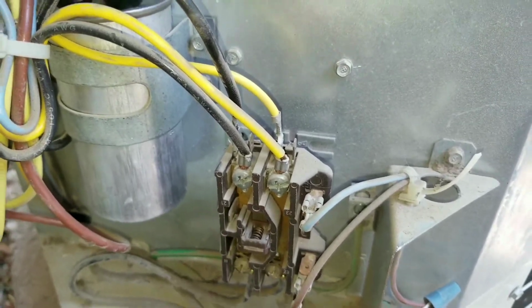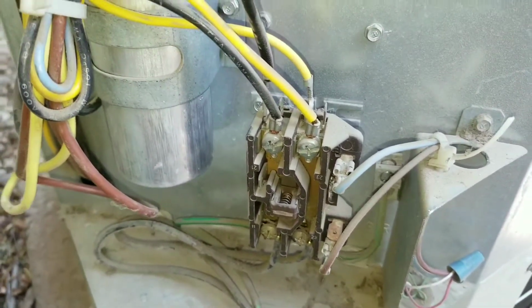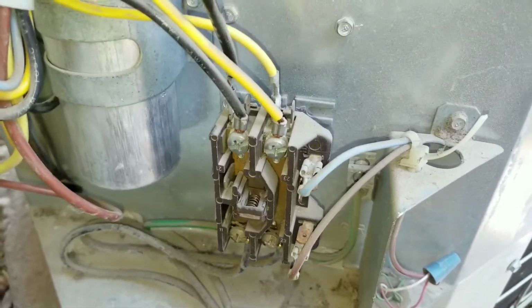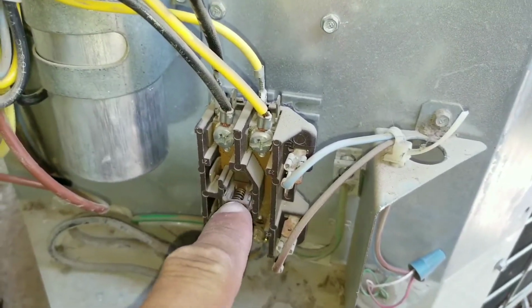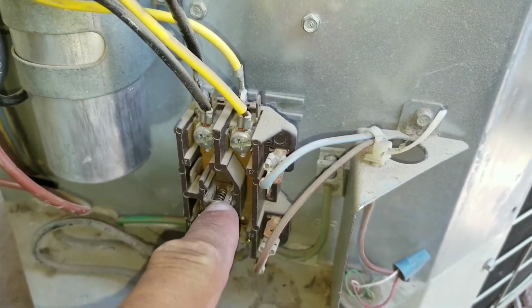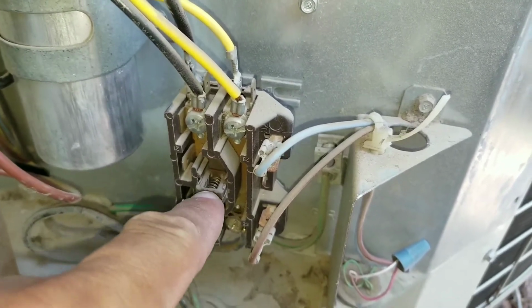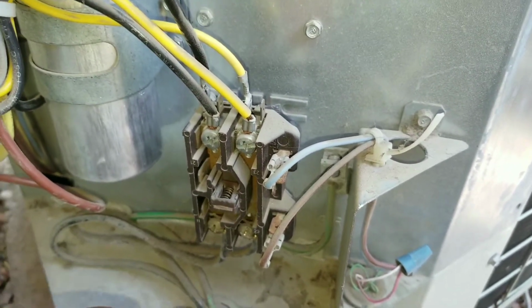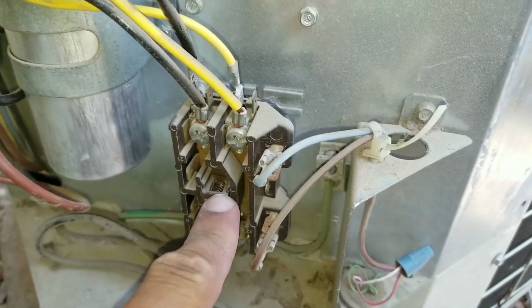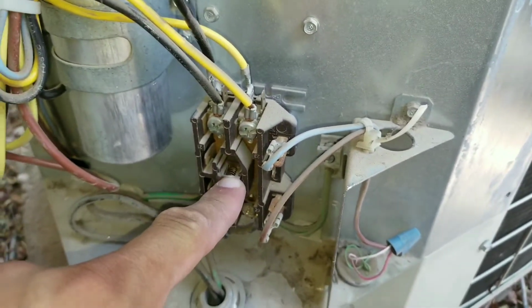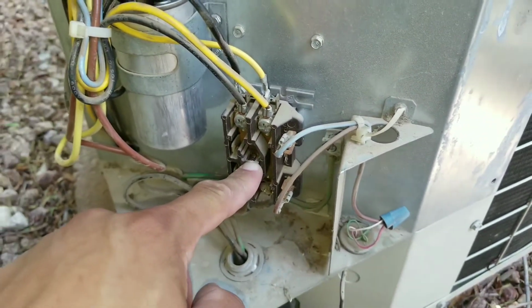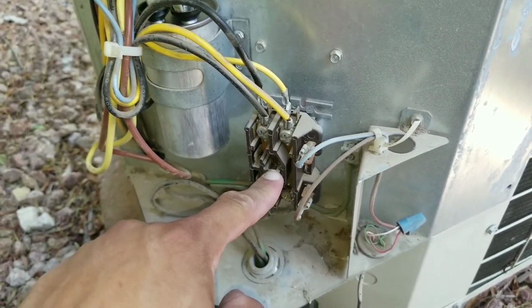Now what I always recommend to my technicians when working on ACs is we're going to manually engage this contactor by pushing this button right here. Once we push that button in, I want to see if my condenser unit will turn on. So I did hear the compressor turn on, my fan motor turned on.